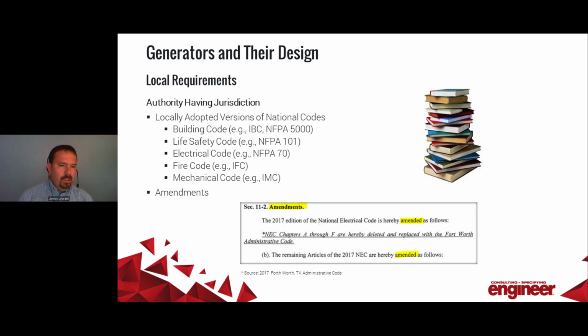So the building code, for example, you could be surprised by the requirements that are applicable to generator installations in the building code. But Chapter 27, which is the electrical section of the building code, has a significant amount of requirements for things like room partitions around your generator, or the runtime of the generator, or the transfer duration when you have a loss of normal service, etc. The life safety code, as the name implies, the code deals with things pertaining to the preservation of human life. You'll find a requirement in there for 90 minutes worth of runtime on illumination for egress path and exit signage throughout the building. Of course, you're all familiar with the National Electrical Code.